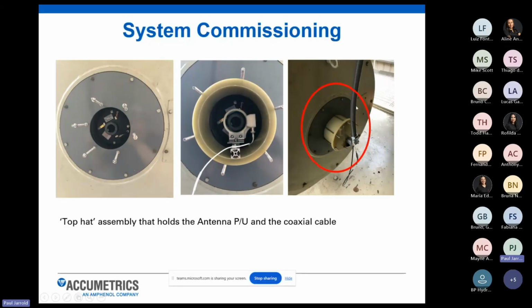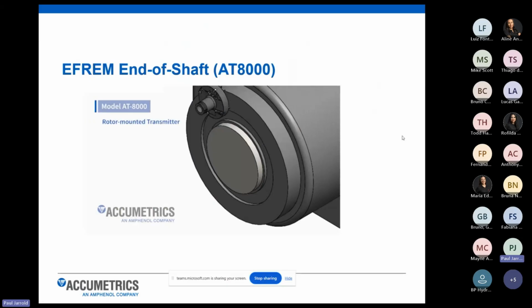And then the image on the right shows you a more finalized version. So everything inside the red circle will be provided by Accumetrics. The only thing we don't provide is the conduit that runs the BNC cable off to our receiver. That's a responsibility of the plant technicians or electricians, to run a conduit for us to route our cable off to the receiver. So this is again showing you an example on a 3D image of what that looks like.